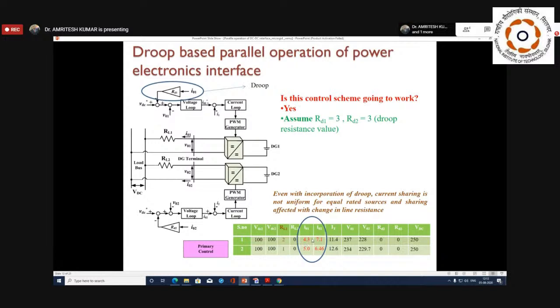Okay, then you can see here, now with serial number 2, I have again considered the line resistance as 1 only. With the incorporation of this droop resistance, RD1 3 ohm, RD2 3, the current sharing IC1 is 5 ampere and IC2 6.46. Both are trying to maintain the DC link voltage as V01 234 and V02 229.7, and this common DC link voltage should be again equal to V02 only.